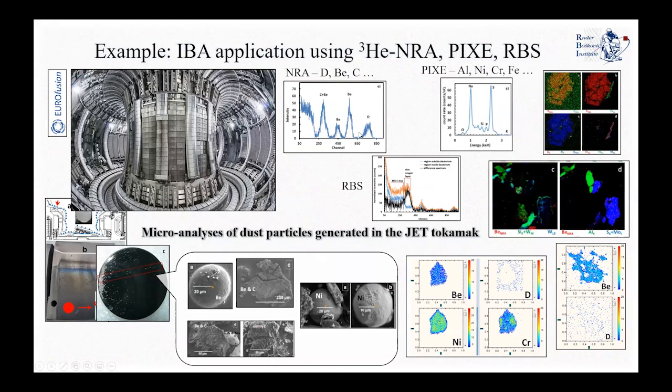These protons are at a high energy part of the spectrum, background-free, which results from the energy the protons gain after the reaction due to the Q-value of the nuclear reactions. With NRA, we can obtain deuterium, beryllium, carbon, boron, and other light elements if present. Combined with PIXE and RBS in parallel, you can obtain information about heavier elements — with PIXE you can measure aluminum, nickel, chromium, iron, and even heavier elements.